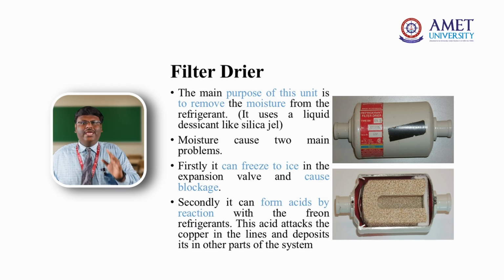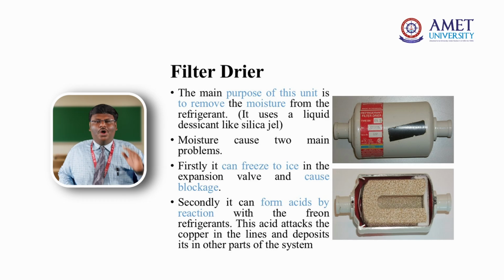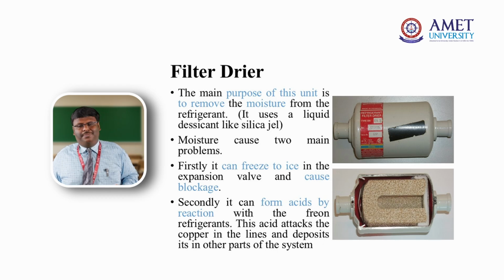the refrigerant. Why moisture needs to be removed is, the temperature at the expansion valve outlet can be 1 degree or 2 degree. So at 1 or 2 degrees, if refrigerant enters your expansion valve with moisture content, the moisture will freeze into ice. In order to avoid ice formation inside the expansion valve, a filter dryer is employed before the expansion valve to remove the moisture content present in the refrigerant.